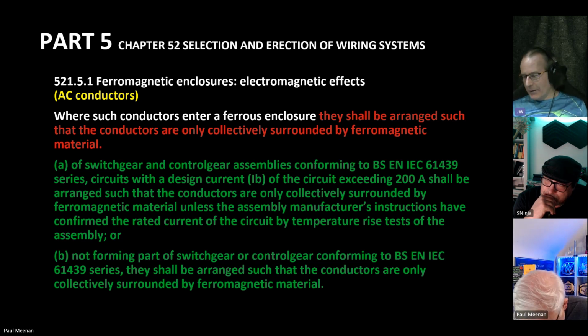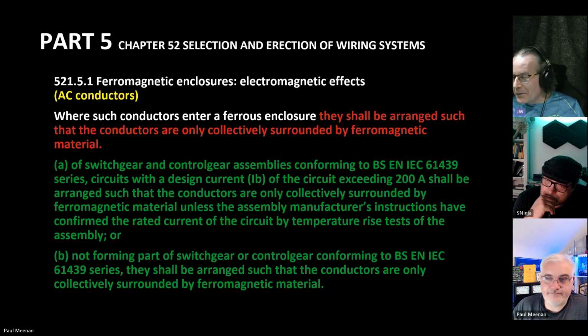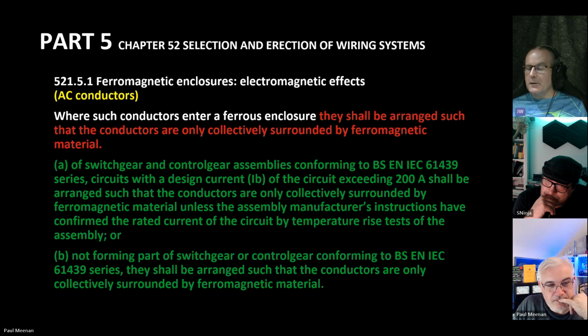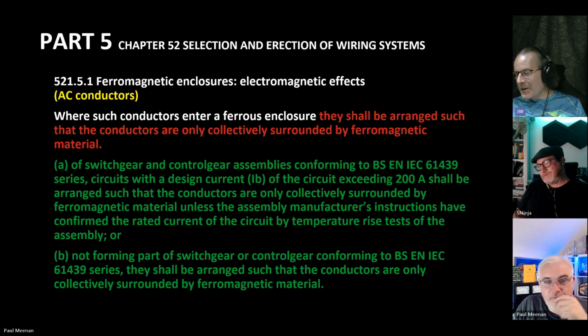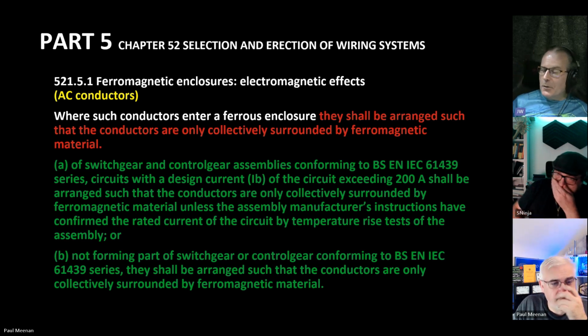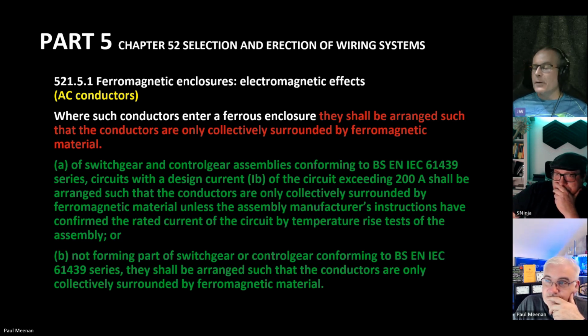In other words, if the manufacturer says you don't have to do that, you can stick the conductors through separate individual holes and then to hell with the rest of the overheating. Or B, if it's not part of that particular standard series, then they shall be arranged so the conductors are only collectively surrounded by ferromagnetic material. So in other words, you still have to put them through one hole, unless the manufacturer says it's perfectly okay, in which case you can stick them through multiple holes and some overheating may occur, and that's perfectly fine because they've already tested it.